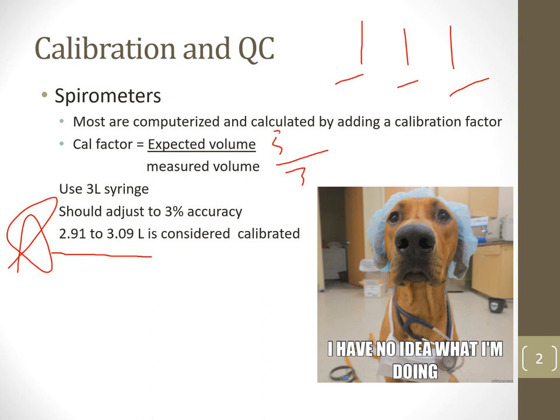You need to understand whether it's within calibration or outside of it. What's the danger? If you don't calibrate the equipment the day of a pulmonary function test, and there's no calibration done that day, there are factors that could lead to a patient being misdiagnosed regarding the severity of their condition—especially if the flow rate or volumes were off during that patient's exam. There can be very serious consequences if the equipment isn't calibrated.